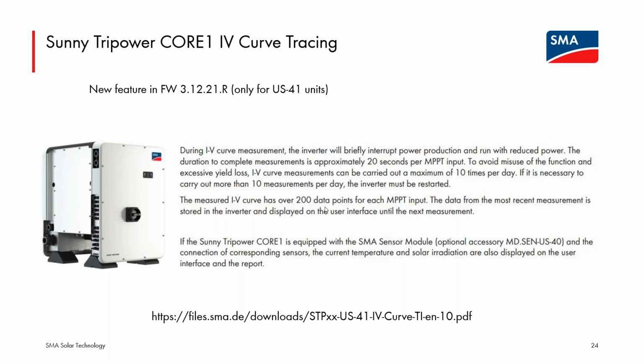It stores several hundred data points for the curves for each of those inputs. If the sensor module accessory card has been installed in the CORE1 and temperature and irradiance measurements are available there at the inverter, those values will be logged with the curve. So you'll have the irradiance and the temperature to be able to benchmark the performance against STC or whatever your other historical performance curves are.